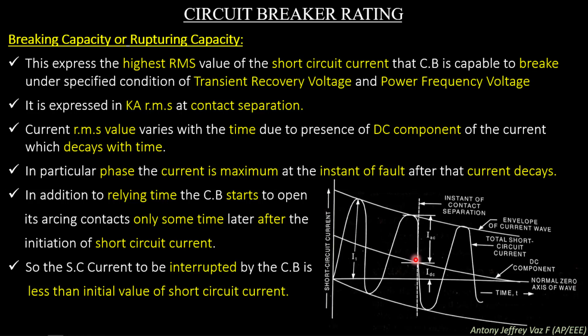So the short circuit current to be interrupted by the circuit breaker is less than the initial value of short circuit current. We can check that the maximum value during the short circuit is at this point. When the contact is opening, you can see the current value is lesser than the initial value of short circuit current. This is stated from this figure, and you can also see the DC component of the current wave goes on decreasing toward zero after the contact is breaking. Then it suddenly goes to zero for the next cycle.